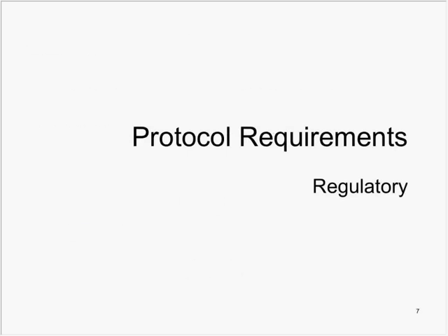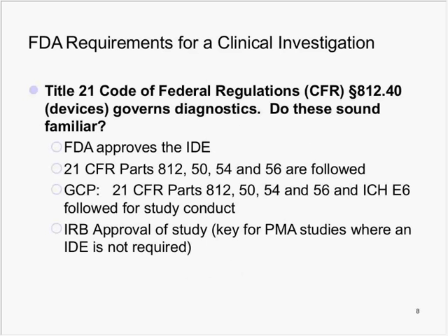Thank you. All right, let's talk about protocol requirements from a regulatory perspective. What does the FDA require for a clinical investigation? Basically, protocols are governed by 2 different overseeing bodies, if you will. There's the Title 21 Code of Federal Regulations, or CFR, and for diagnostics, it's 812. And if you're familiar with pharma, it's the same thing except it's 312.